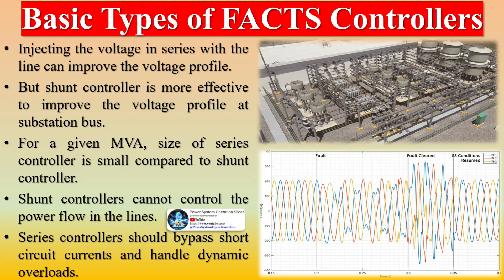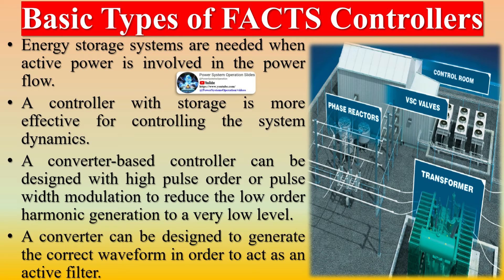Shunt controllers cannot control the power flow in the lines. Series controllers should bypass short-circuit currents and handle dynamic overloads. Controllers with gate turn-off devices are based on DC to AC converters and exchange active and reactive power with AC lines, requiring an energy storage device. Energy storage systems are needed when active power is involved; a controller with storage is more effective for controlling system dynamics. A converter-based controller can be designed with high pulse order or pulse width modulation to reduce low-order harmonic generation to a very low level. A converter can also be designed to generate the correct waveform to act as an active filter.